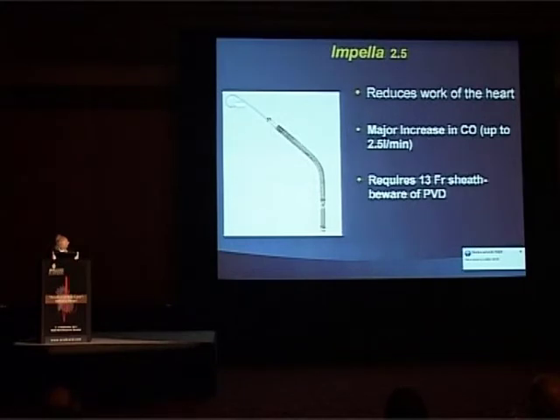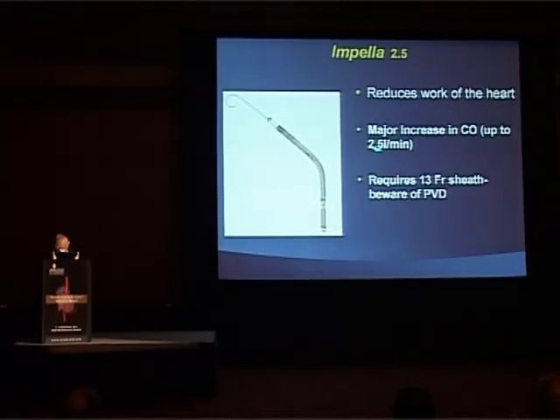This is a pigtail catheter with a motor drive so that blood is sucked out of the left ventricle and pumped into the aorta. It can increase the cardiac output up to 2.5 liters per minute—they call this the Impella 2.5. In fact, the cardiac output can increase up to 2.5 liters per minute, but often the real value is more like 1 to 1.5 liters per minute.